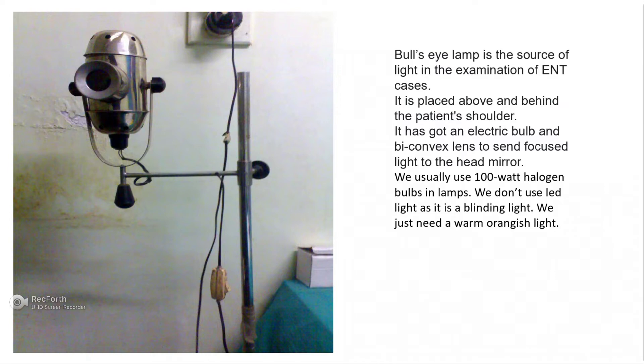We need a warm, orange-kind of light. When doing an examination, if there is too much light in the room, switch off some lights or pull the curtains and keep a moderate amount of light. The bull's eye lamp is a cylindrical box — do not touch it directly as it gets heated from the 100-watt halogen bulb and can burn you. Inside it has a bi-convex lens and the 100-watt halogen bulb.